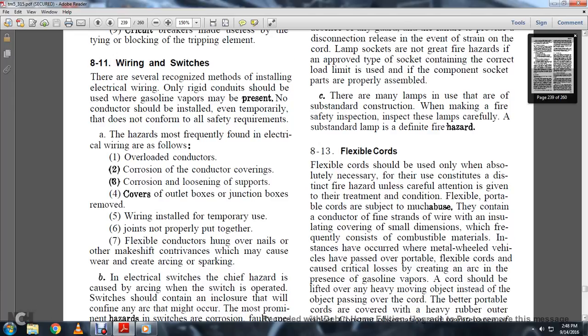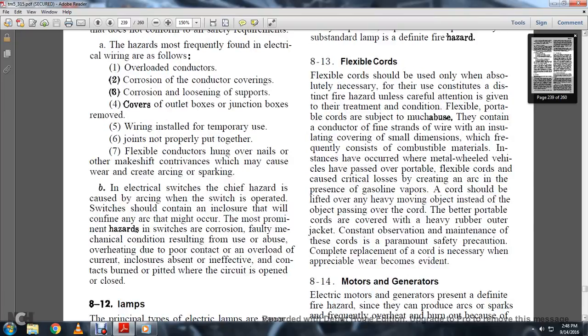Wear and tear may create arcing and sparking. In an electrical switch, the chief hazard is caused by the arcing when the switch is operated. Switches contained within an enclosure will confine the arc, but the most prominent hazards are switch corrosion, faulty mechanical condition resulting from use or abuse, overheating due to poor contact or overload, and defective contacts burned or pitted by the current when the circuit is opened or closed.